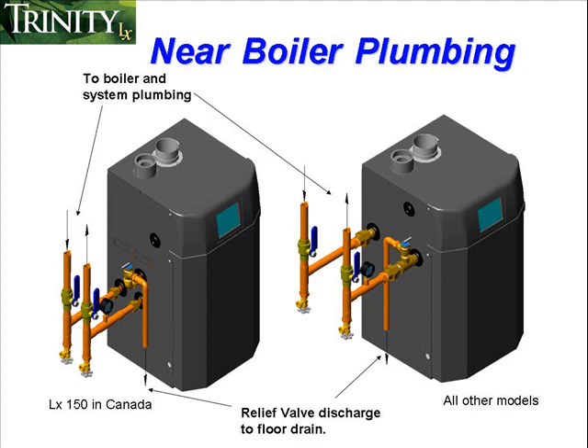If the relief valve is installed with the incorrect orientation, for example horizontally with the drain pipe out of the bottom, it may not function properly, resulting in property damage or personal injury. Ensure the discharge of the pressure relief is piped to a location where the steam or water will not cause property damage or serious injury.